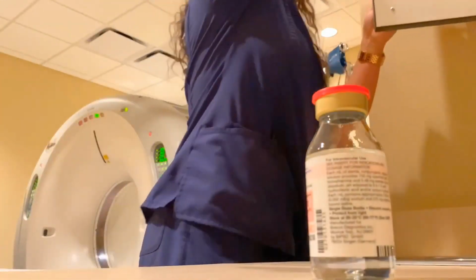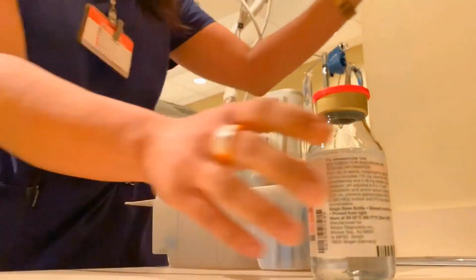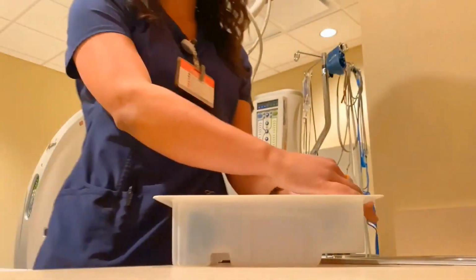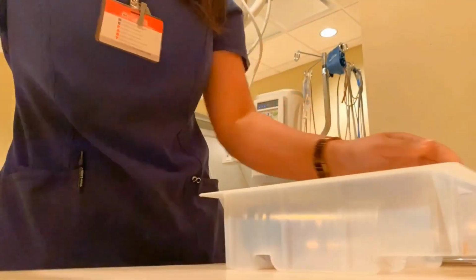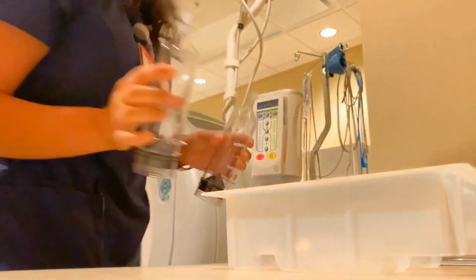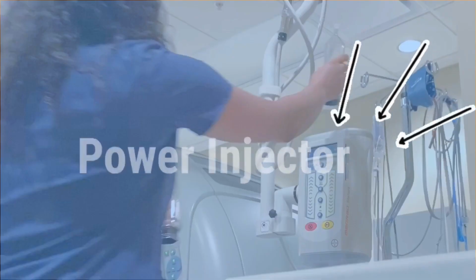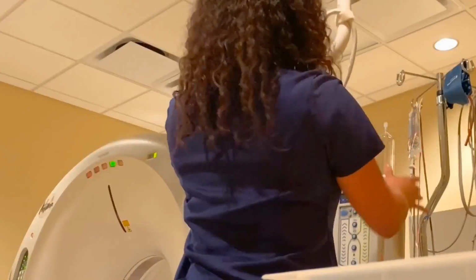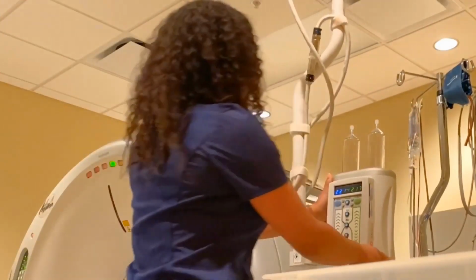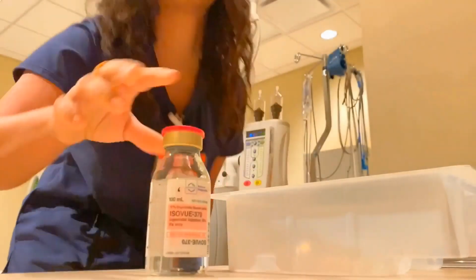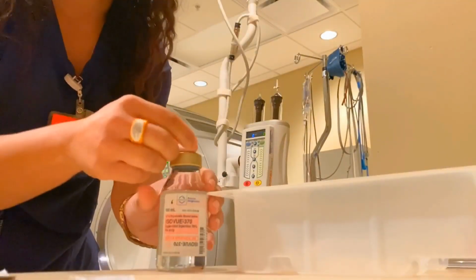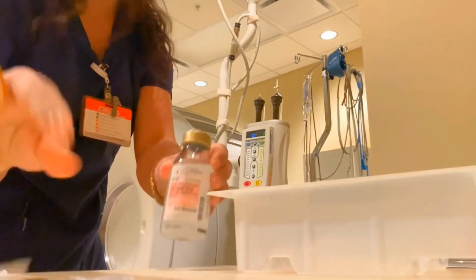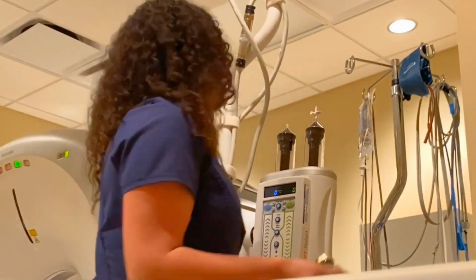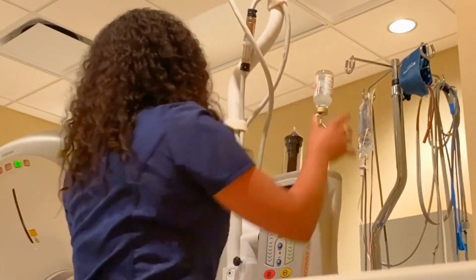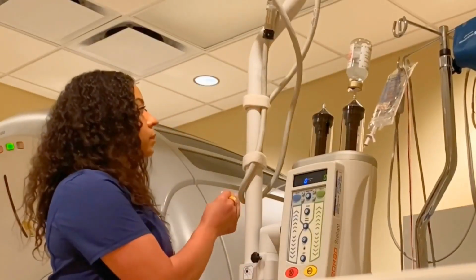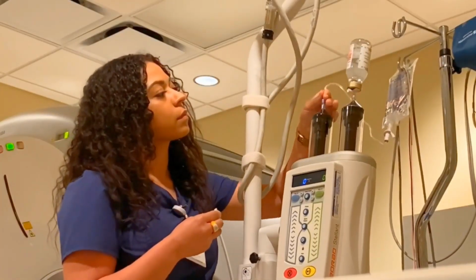So now you'll actually watch me set up the IV contrast and get it ready for a patient. We have these pre-made kits that we use to load the power injector, and this is the power injector. This allows us to inject the contrast without us being in the room, exposing ourselves to the radiation. Since we use the console to set up exactly how much contrast and how much saline we want to administer, the power injector is really smart, and it'll draw up the contrast and saline to that exact volume.